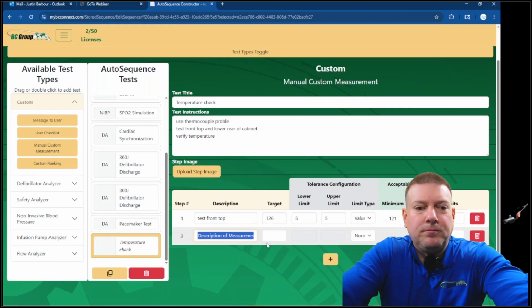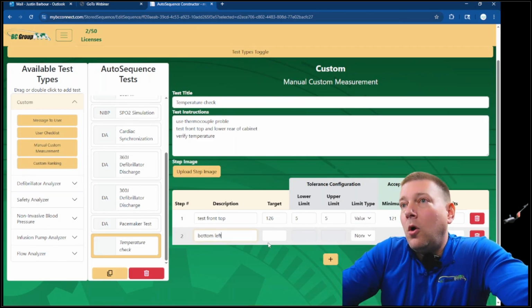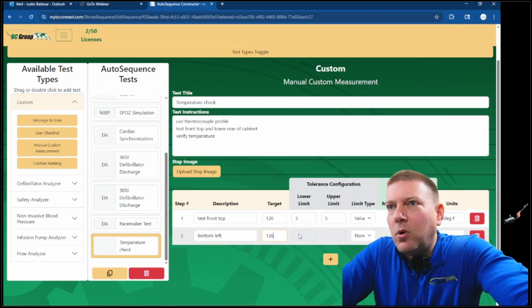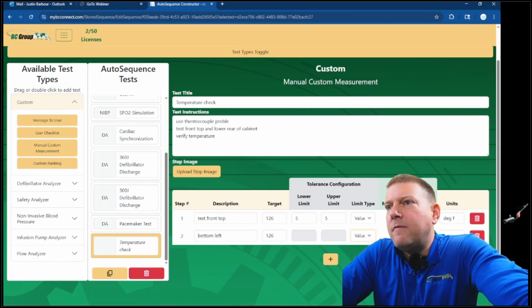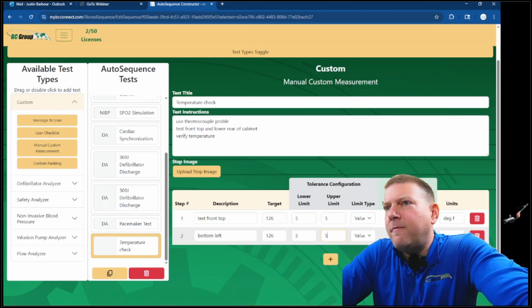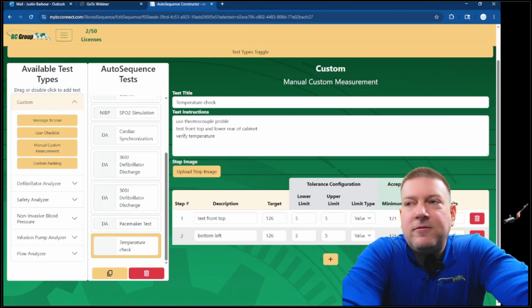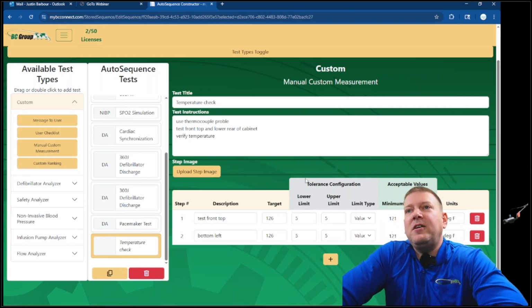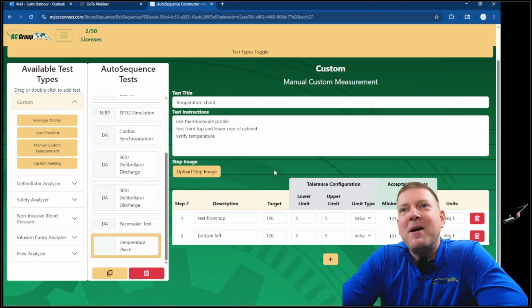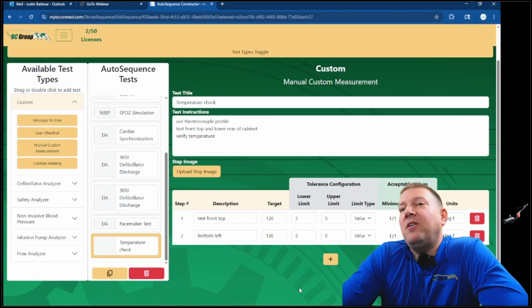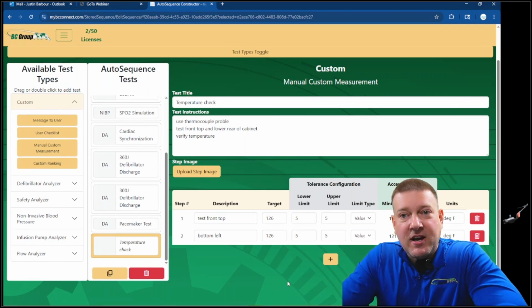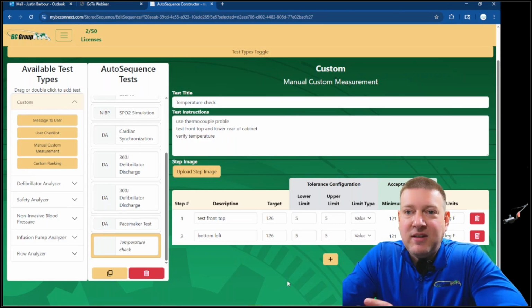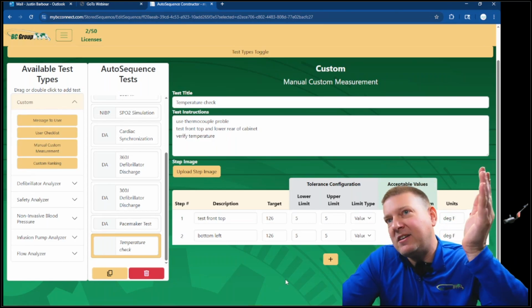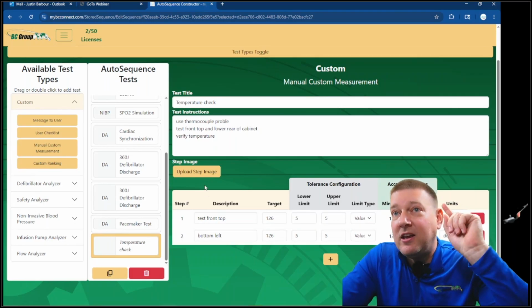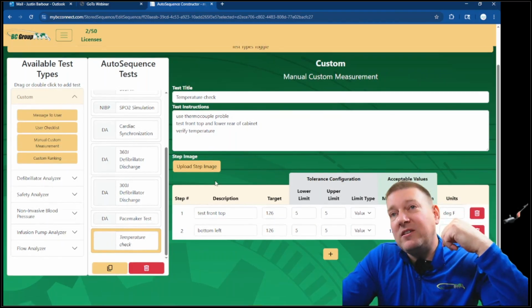Okay, and I did the top front. Let's do bottom left. Again, 126, of course. Value 5 and degrees Fahrenheit. And there it is. I just added an entire step, completely unnecessary step to my defibrillator PM. And I'm telling them that I want to incorporate temperature checks. Now, there's no way of doing an automated temperature check at this time, but I told them where I want them to test, and I told them what test equipment I want to use. I can include a photo of what test equipment they should be using or where I want them to test on the cabinet.